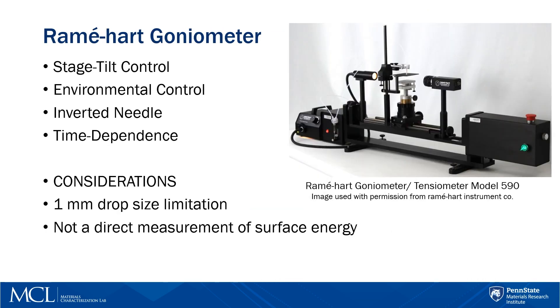The instrument used to make these measurements here at the MCL is the Rame-Hart Model 590. It's called a goniometer tensiometer because it can measure both the contact angle and drop shape, giving information about surface energy and surface tension respectively. Some capabilities include tilting the stage to deconvolute the effects of gravity and other surface tension components. Our environmental control attachment allows us to raise the temperature up to 250 degrees Celsius and operate from a low vacuum up to 0.6 atmospheres. An inverted needle and quartz cell attachment allow for liquid-liquid studies, inverted sessile drop, and captive drop experiments. The instrument also allows multiple data acquisitions spread out by a specified time interval, enabling time-dependent studies.